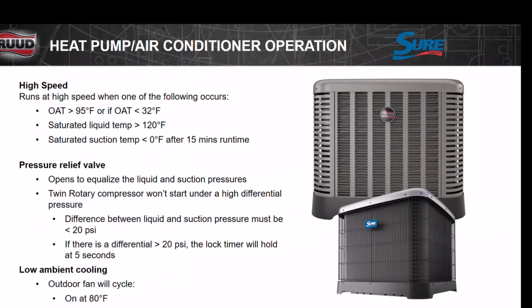The heat pump will run at high speed when the following occurs. You know, our outdoor ambient temperature is 95, or the outdoor ambient temperature is below 32 degrees. Saturated liquid temperature. A lot of things are going to affect what speed the unit runs in. If the saturated temperature is below zero after 15 minutes of runtime.